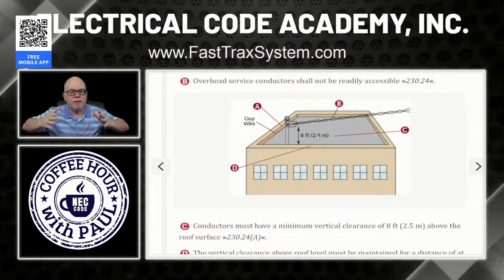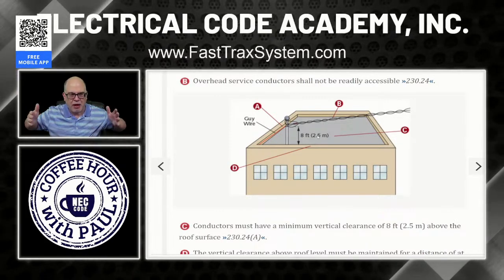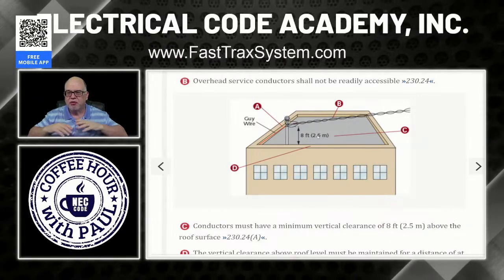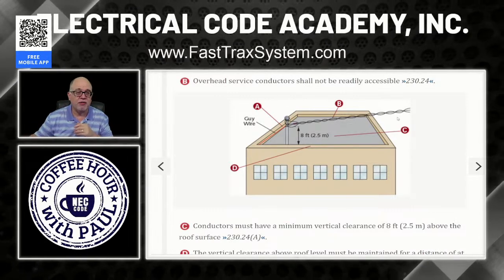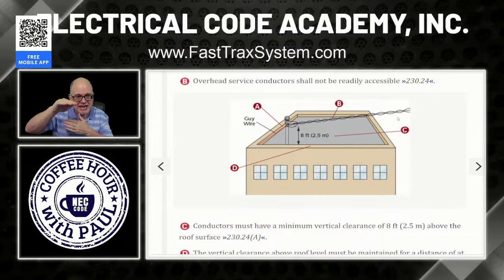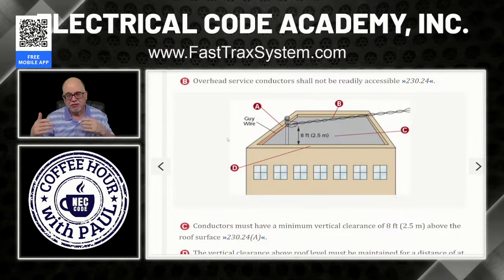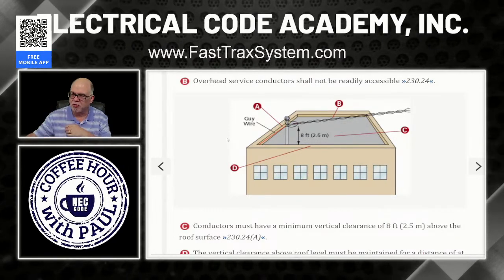And so you kind of think of this whole roof. It encompasses this whole roof, but it extends out 3 feet beyond the perimeter of the roof. So it's out 3 feet and up 8 feet. So it's basically like putting a cap on top of it, if you will. So that's where you have to maintain this clearance. And it has to be, starts at the 3 feet from the roof, and it has to be at that 8 feet and maintain that all the way to the point of attachment. Okay. So that's kind of the general rule. We're not talking any of the exceptions in this episode. That's kind of the general rule for that.